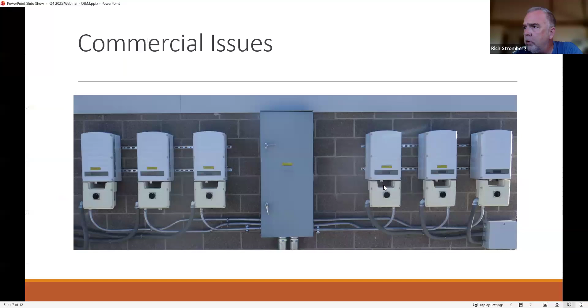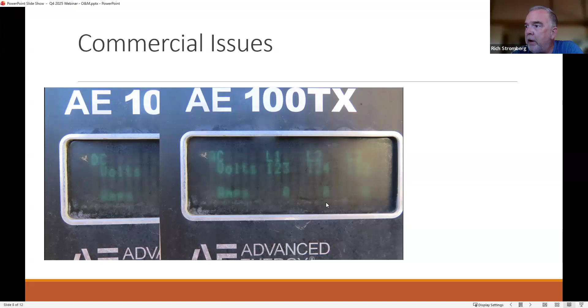Here's another system owned by that same organization. They had a single 100 kilowatt central inverter on the ground outside the building, on the backside. Before going up on the roof, I checked the inverter and could see it was in a fault state. We have DC volts but no amps. On the AC side, it's connected 208 3-phase, but no amps going out.